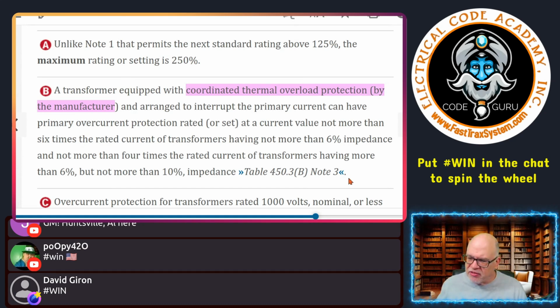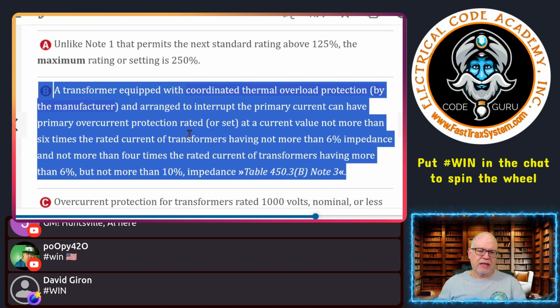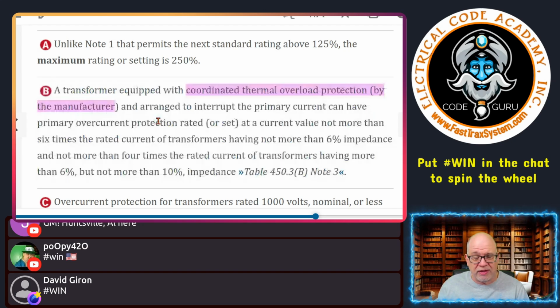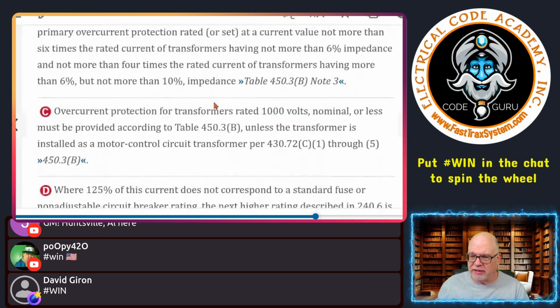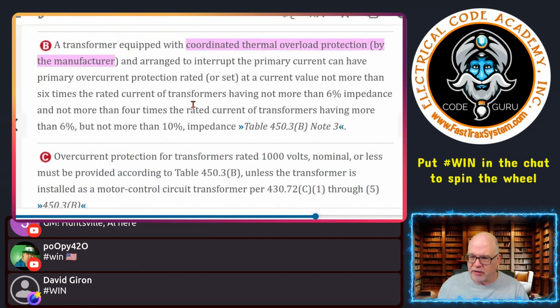I do not see many of this, okay? I've seen a lot of transformers, and I think it's probably primarily due to the cost of the transformer itself, and then dealing with one that might have some coordinated thermal overload protection, and it's costly. So it's typically a standard dry type transformer. It would not have that coordinated thermal overload in it. So you really don't fall into this one here.